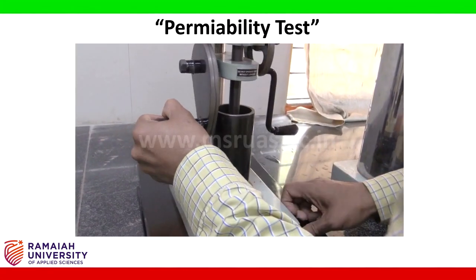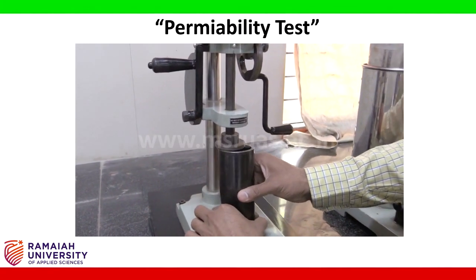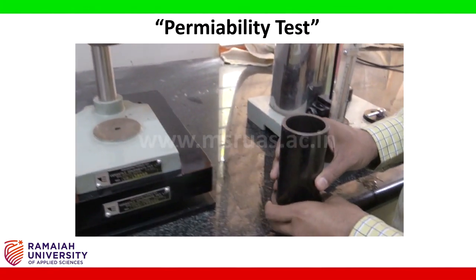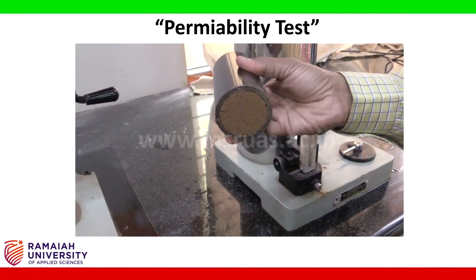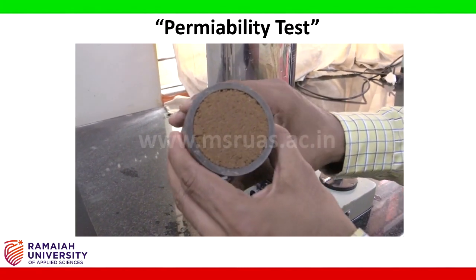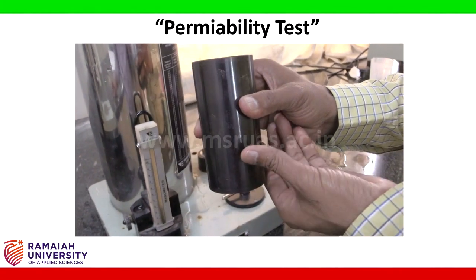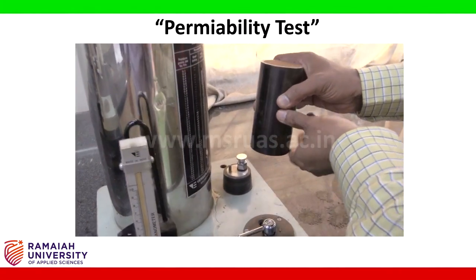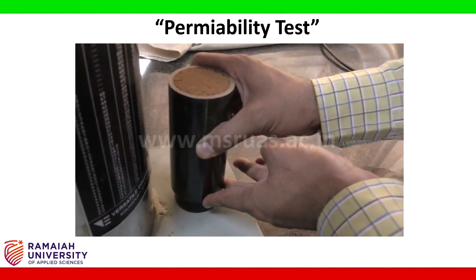Operate the lifting cam and take out the specimen tube and separate the plunger cap. Do not remove the sample from the sample tube, and with the inverted position, place it on the large orifice position.